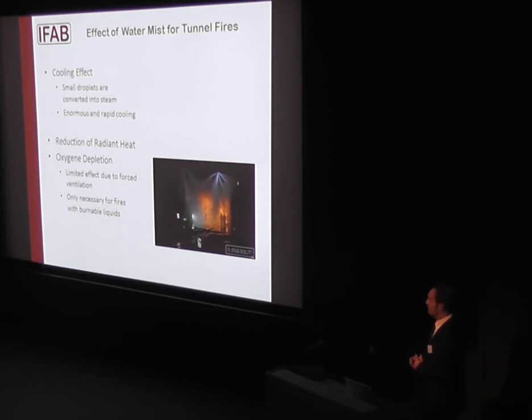What's also a big reason water mist gives good results is the reduction of radiant heat compared to a sprinkler or deluge system — using the correct wording, the reduction potential is much higher, so you can even stand really close to a really big fire, 50 megawatts, standing 5 or 3 meters away, and it's no problem. You feel it on your skin, but without water mist on, it would be impossible.